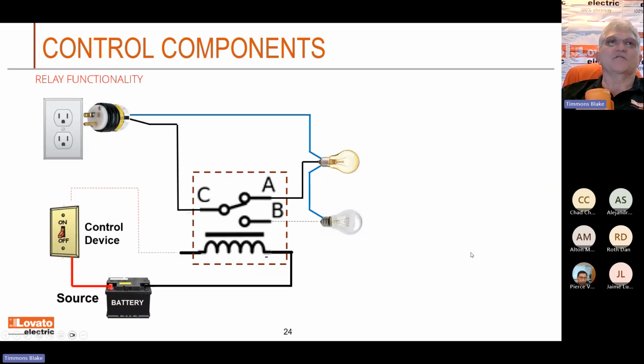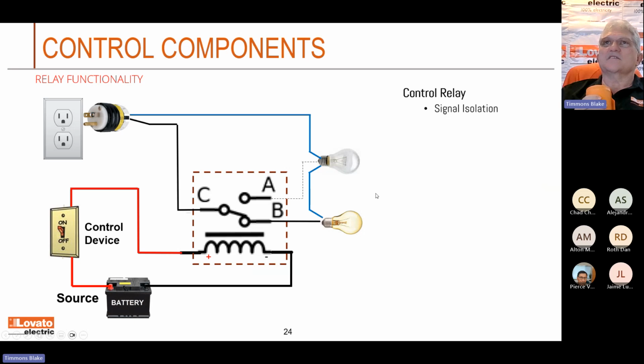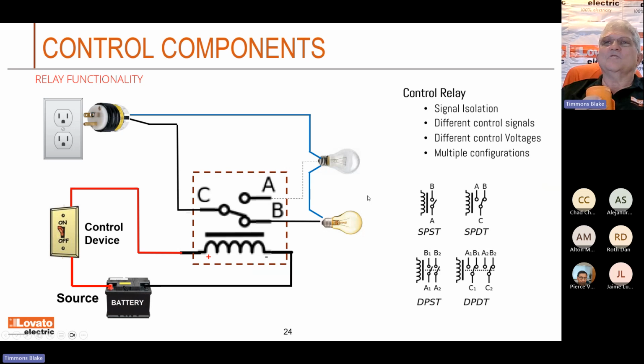Let's talk about that. Here's a little bit of animation on the isolation. You can see here, I have a battery powering up a relay right here to turn on 110 volts. You surely wouldn't want to mix the two. So when you turn it on, you can see the contact switch on that thing. You see my load switches too. Okay, so you'll see this load switching, and we call this a changeover contact. Okay, so it's got a normally open and a normally closed, and it changes over from one source to the next. Okay. Control relay, signal isolation, different control signals, different control voltages, and multiple configurations.